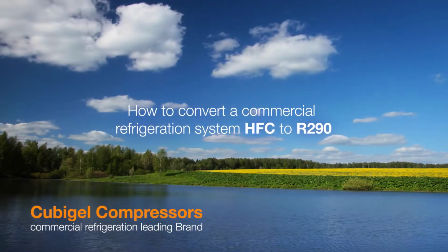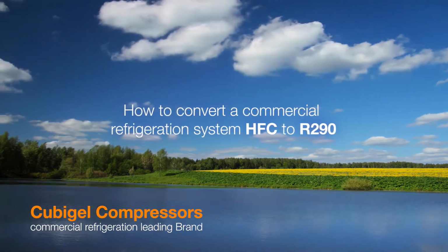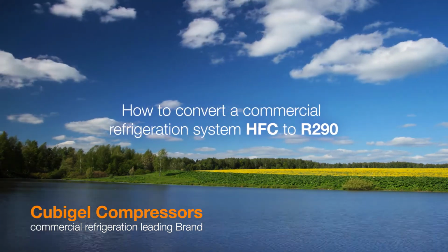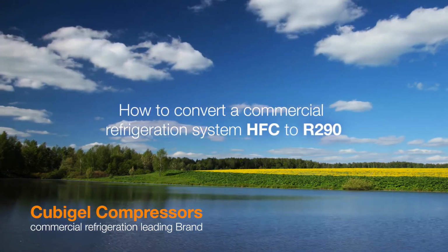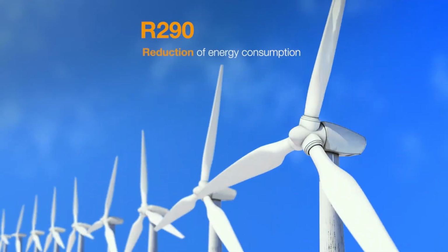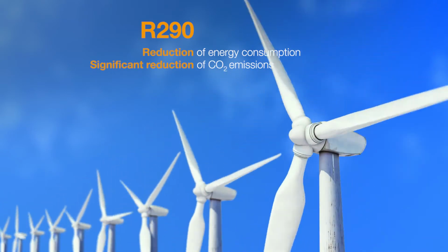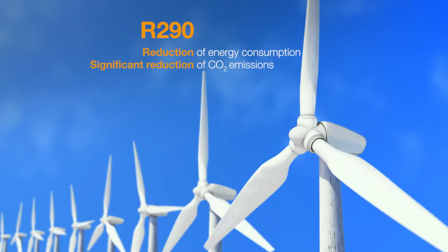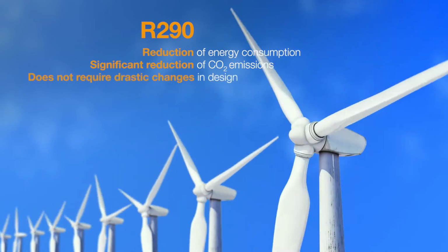In this video, we will see how to convert a commercial refrigeration system that uses HFC refrigerant to one that uses the best option in natural refrigerant, propane R290. Its most significant benefits include the reduction of CO2 emissions into the atmosphere due to the significant reduction in energy consumption and that it does not require drastic changes in the design of the equipment.